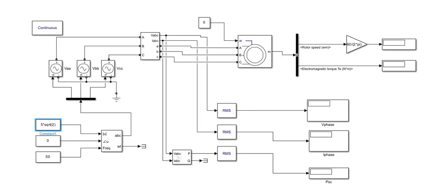This is our test 2. Test 2 is to measure the value of the total impedance ZLR, lock rotor resistance RLR, and lock rotor reactance XLR, with respect to the stator of the 3-phase induction motor. This is my circuit.